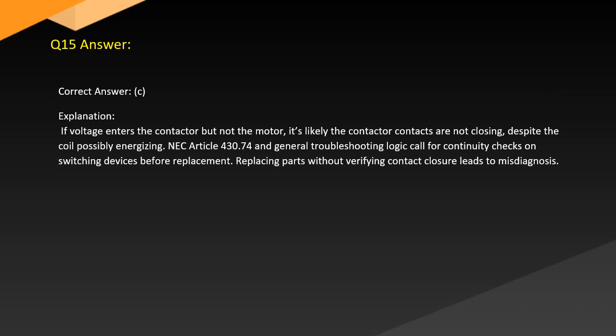Answer. Correct answer: C. Explanation. If voltage enters the contactor but not the motor, it's likely the contactor contacts are not closing despite the coil possibly energizing. NEC Article 430.74 and general troubleshooting logic call for continuity checks on switching devices before replacement. Replacing parts without verifying contact closure leads to misdiagnosis.